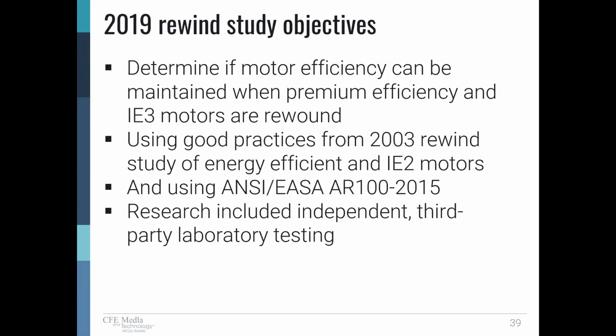So we have the same question. We wanted to determine if motor efficiency can be maintained when premium efficiency and IE3 motors are rewound, using the good practices from the 2003 study of energy efficient IE2 motors and using ANSI EASA AR100. The reason for using AR100 is because it has the good practices that were identified in the 2003 study. Almost all of them were already in AR100, and following that study, they were incorporated into it. So by the time of the 2010 edition of AR100, all of the good practices had been built into the AR100 document.